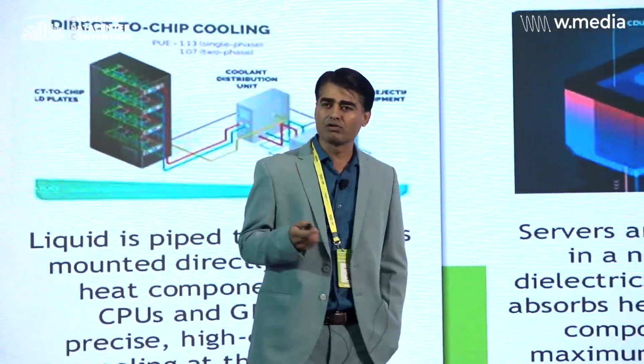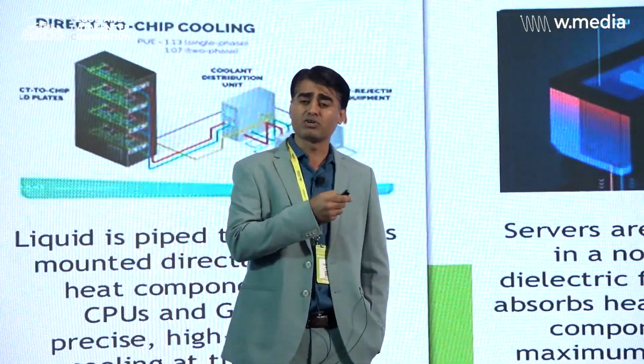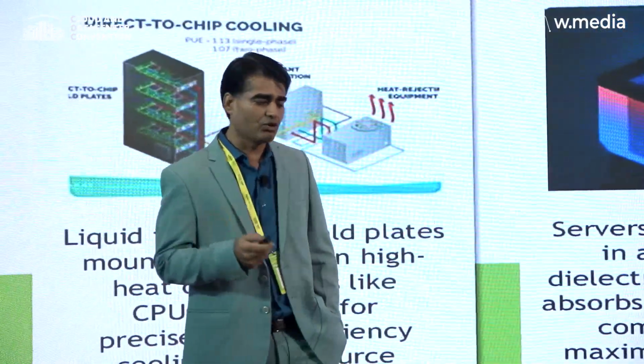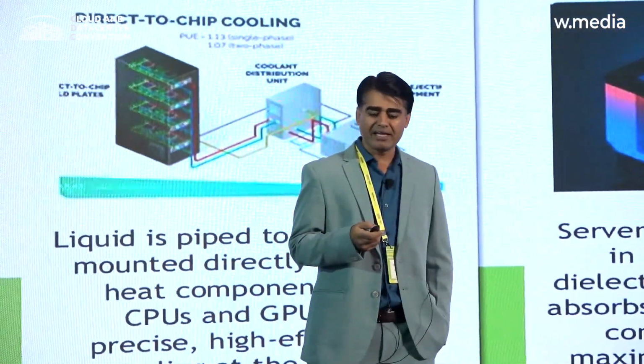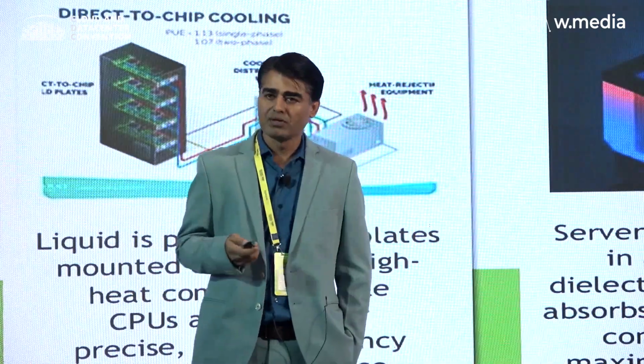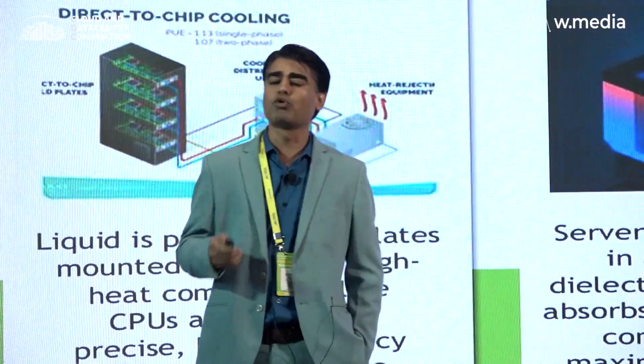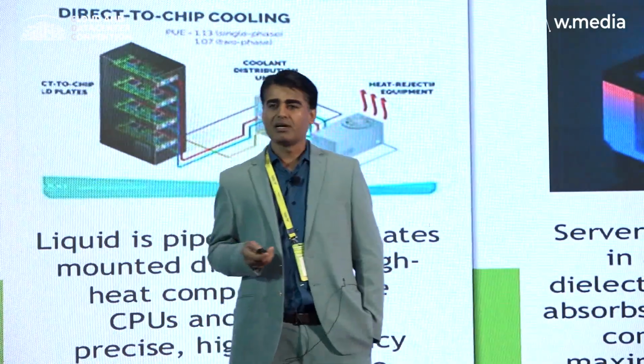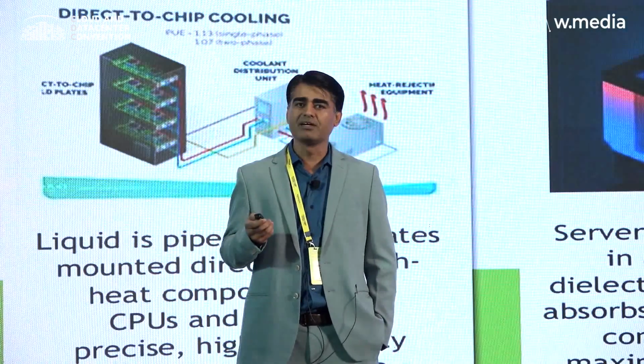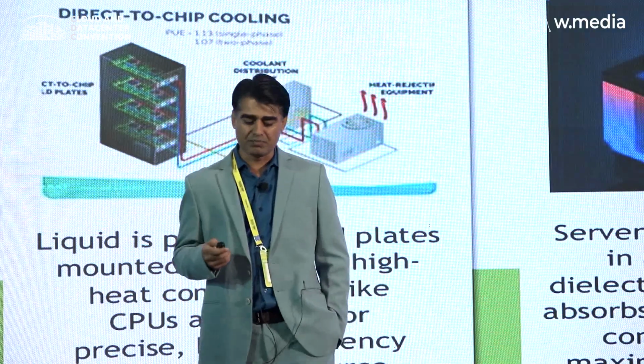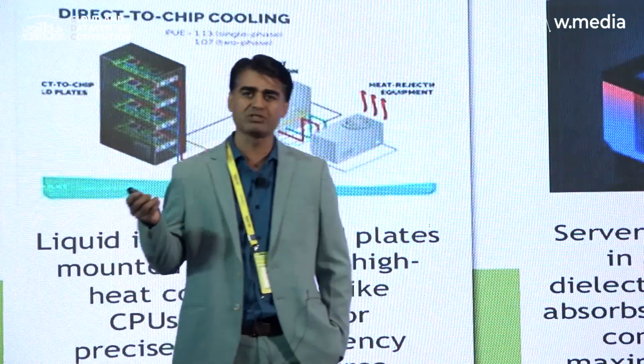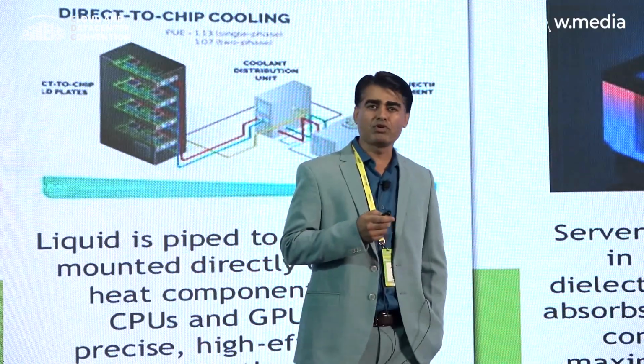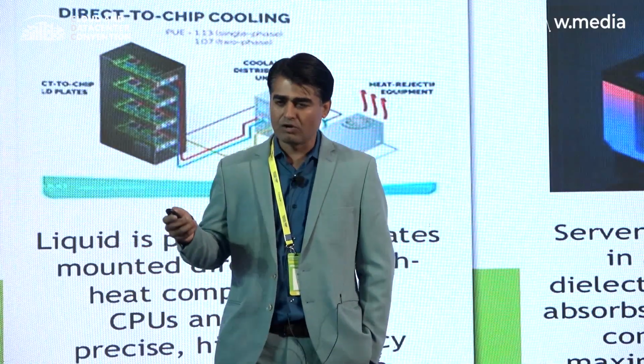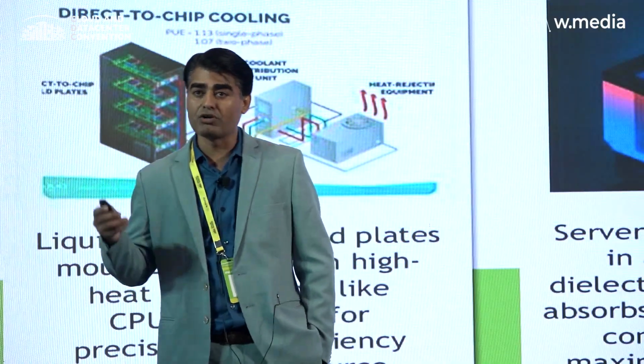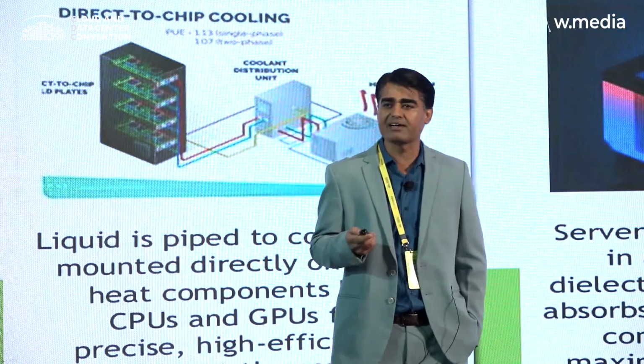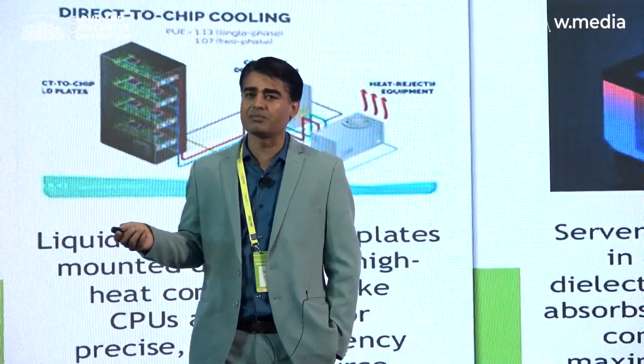We have AI workloads coming in, Janvi was just explaining about it. AI workloads are increasing, and the TDP of every chip is increasing, and as the density of the chips increases, we need more efficient cooling. Air cooling is not going anywhere, it will still be there, but when we talk about the latest advancements in chips, for example NVIDIA announced Vera Rubin, right? So when we talk about 500 kilowatt, 600 kilowatt, or even 1 megawatt contained within a single rack, air cooling is not something that can really cater to it.